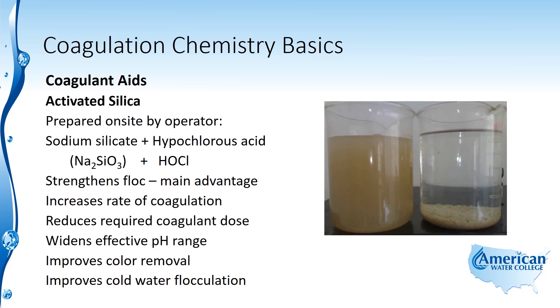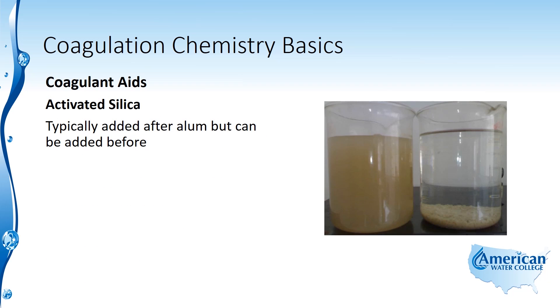If color is an issue, activated silica is effective at removing color. In addition, it improves cold water flocculation, which doesn't occur very well in cold water for a couple of reasons: chemical reactions occur more slowly, and the water is more dense. So when water temperatures drop, activated silica can improve the flocculation process. When using it with alum, it is typically added after the alum.